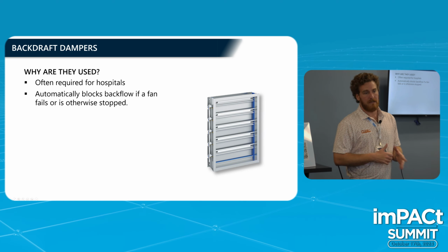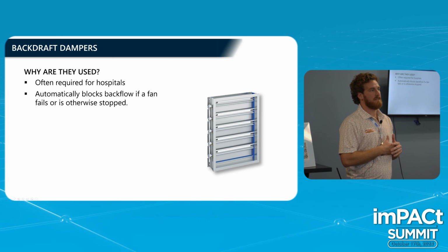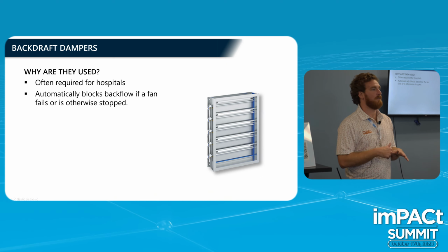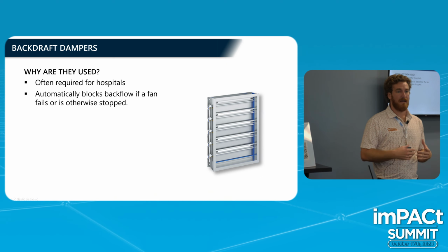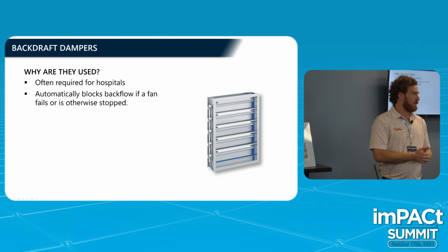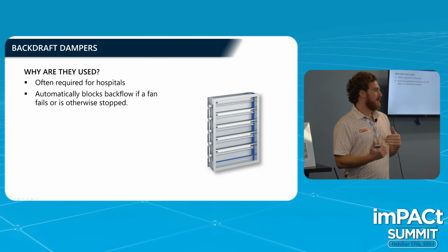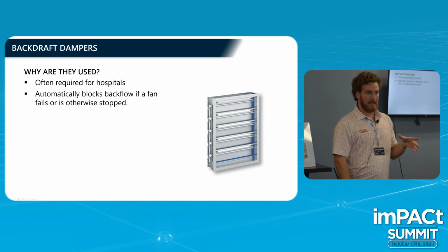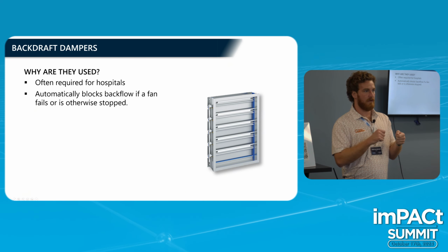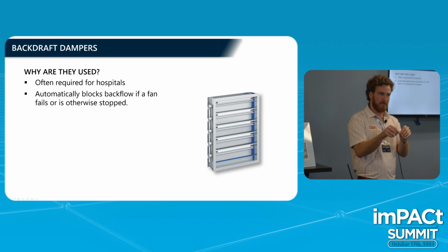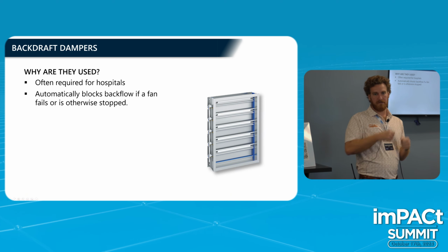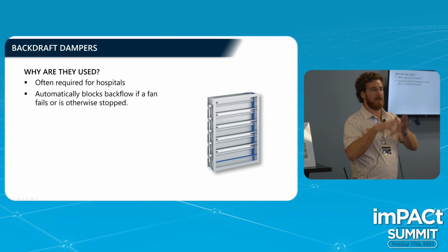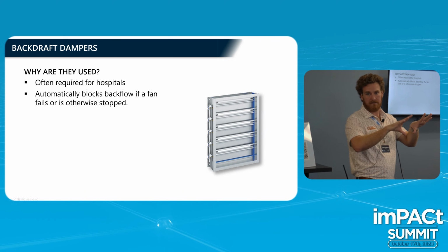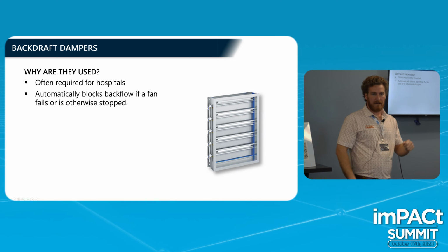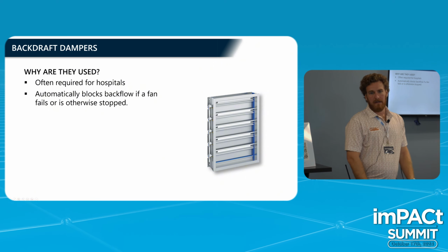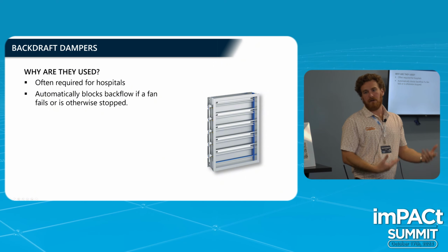They are available, but if it's not a critical application, if you're an office building or a school or something like that, and you have a fan go down, and you've selected for 100% or higher redundancy, then you can just turn the unit off for a few minutes, go in, and take the fan off the wall. They're designed to be easy to install. You can just unplug the plugs from the ledge, undo the bolts, and put a blank off plate in its place. That'll prevent the recirculation. Then you just get out of the unit, turn it back on, and it's going back to normal. So that's our alternative to that.